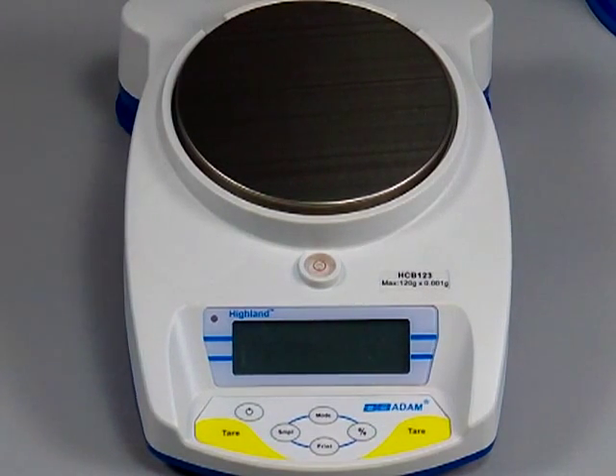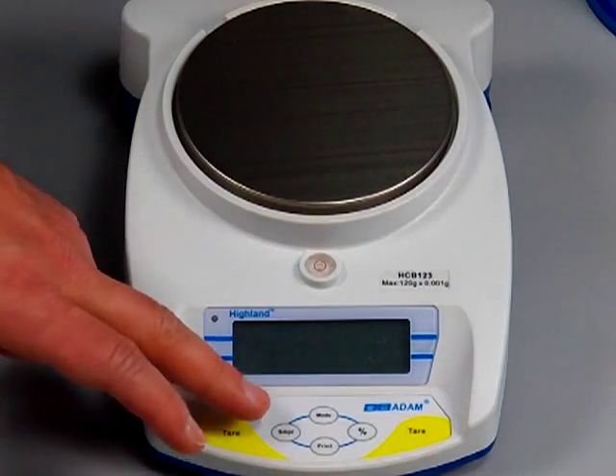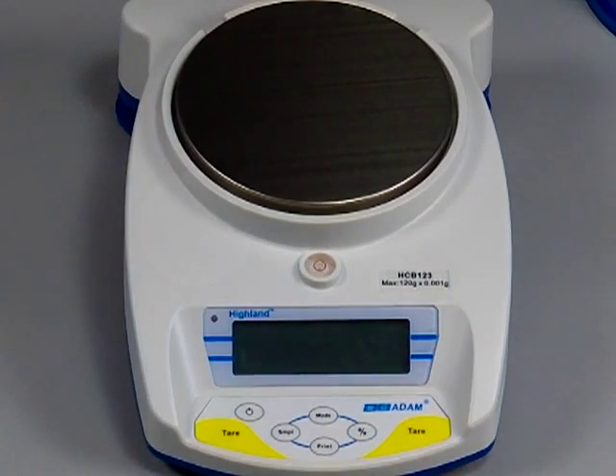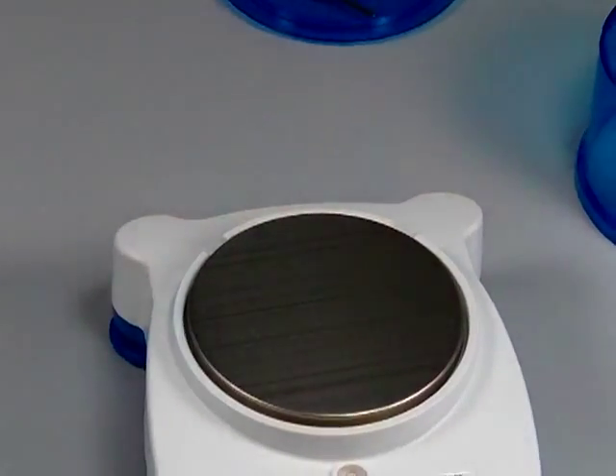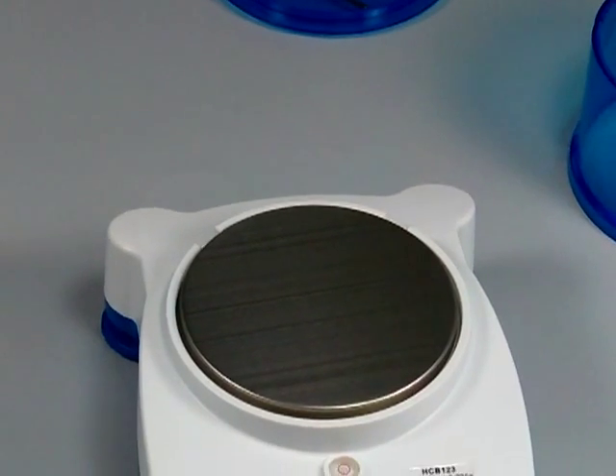But the calibration is really simple. Basically, you power up the balance, press simultaneously the sample and the print key, and the scale will display unload. You simply hit the tare button, and then you can either use an external calibration weight, or you just move this lever that I mentioned on the back of the scale, and it will drop the internal calibration. So that's a real unique feature.